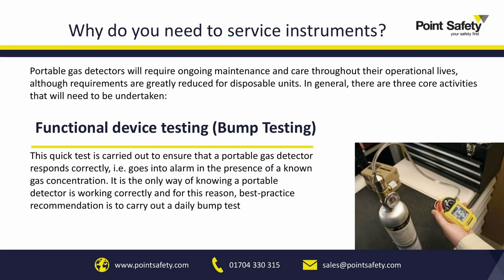Most, especially the toxic meters, read at 0, so you will never know if they're going to pick up their target gas unless you regularly apply a target gas to ensure that is the case. So it is a best practice. Not everyone does implement a bump testing program, but it's highly recommended. And if any of yourselves or your customers do not have one in place, then I think you should start considering it and advising it to your customers. Ourselves or Chris and Spantech are more than happy to go over what gas requirements you may need.